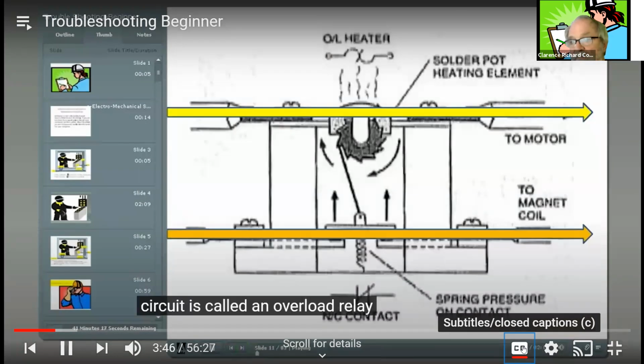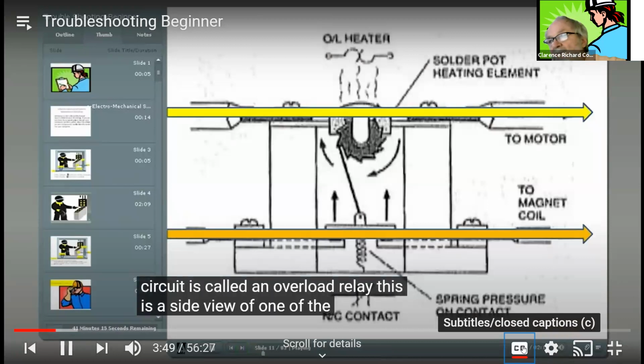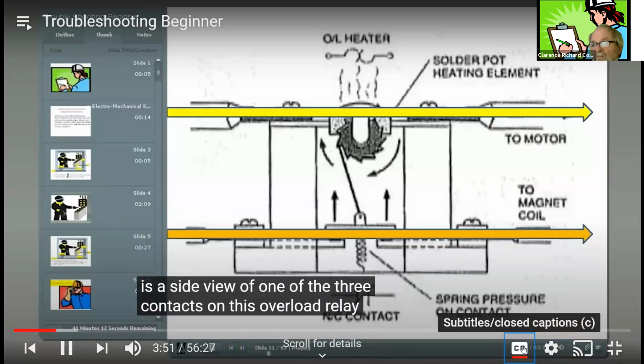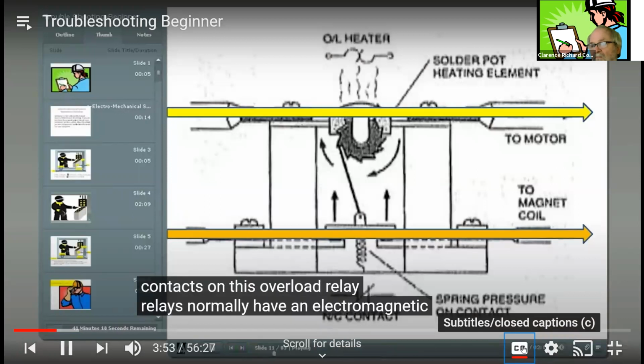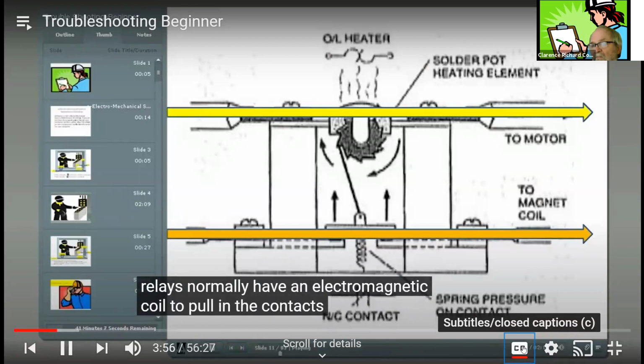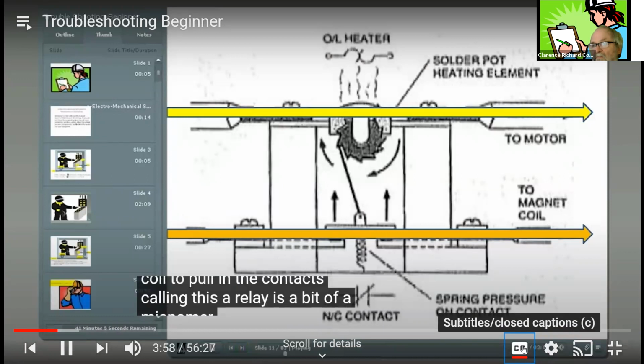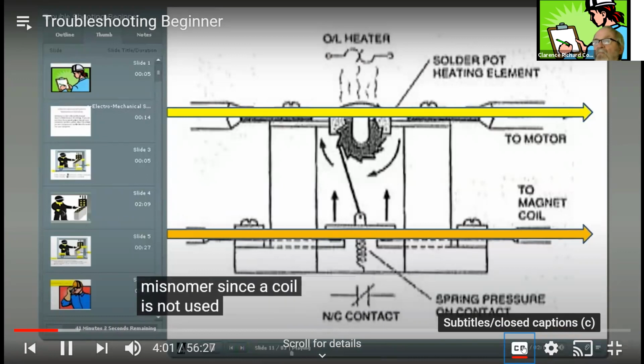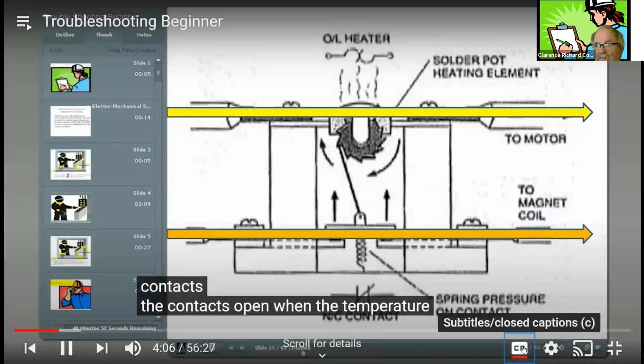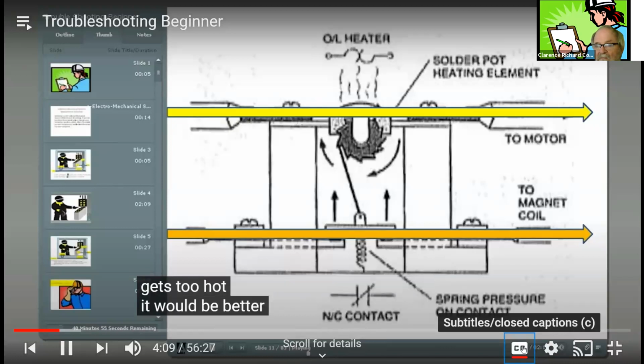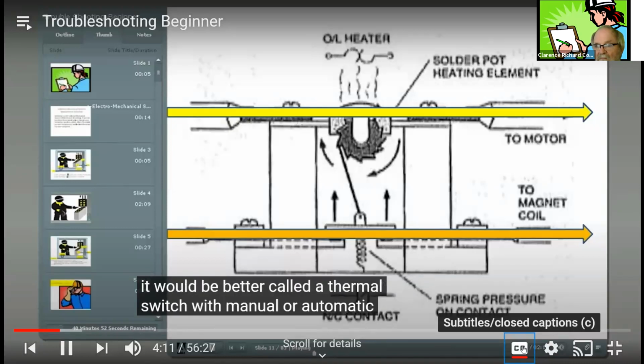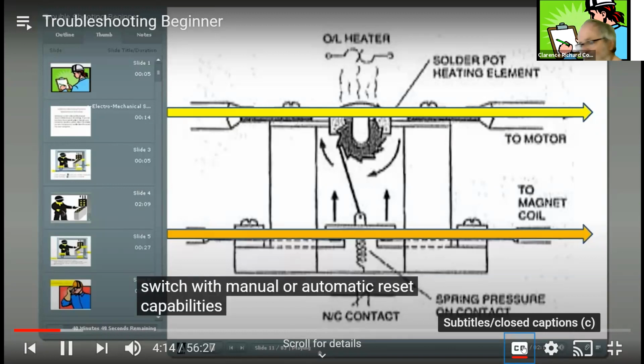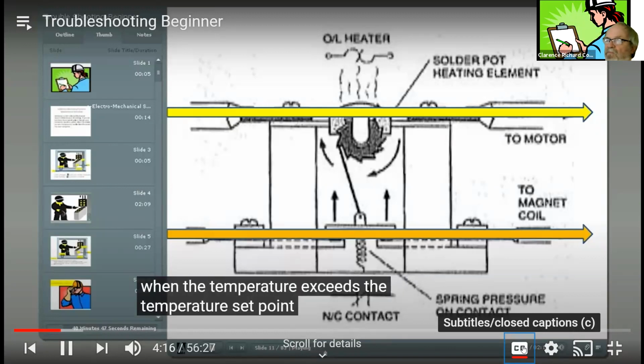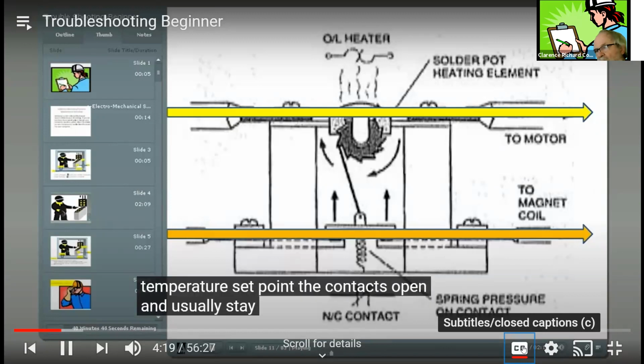The circuit is called an overload relay. This is a side view of one of the 3 contacts on this overload relay. Relays normally have an electromagnetic coil to pull in the contacts. Calling this a relay is a bit of a misnomer, since a coil is not used to open and close the contacts. The contacts open when the temperature gets too hot. It would be better called a thermal switch with manual or automatic reset capabilities. When the temperature exceeds the temperature set point, the contacts open and usually stay open until the contacts are reset.